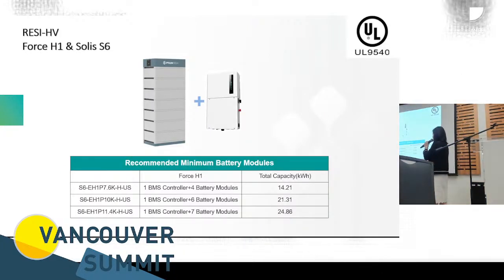For the Solis S6 inverter, we do have some recommendations because this battery has a half C rating. We recommend for 7.6K, use at least 14 kilowatt hours, which is 4 modules. For 10K, we recommend 21 kilowatt hours. For 11K, we recommend 7 modules, which is 25 kilowatt hours.